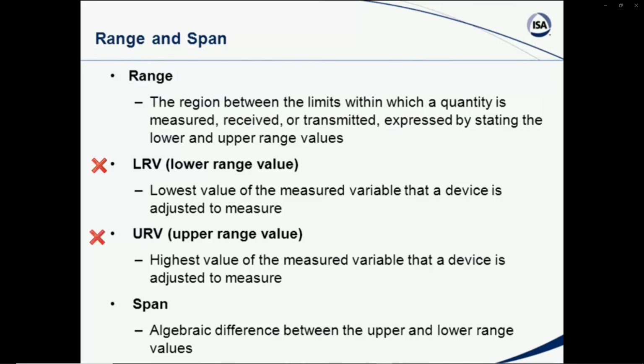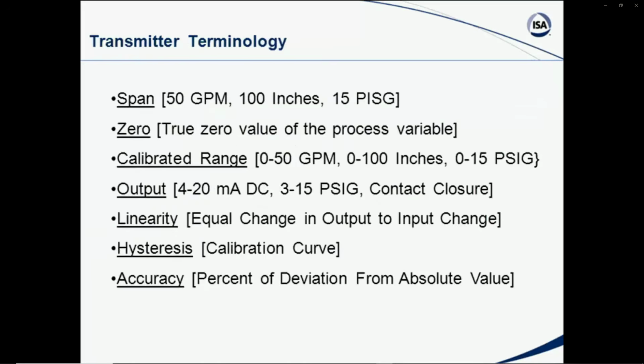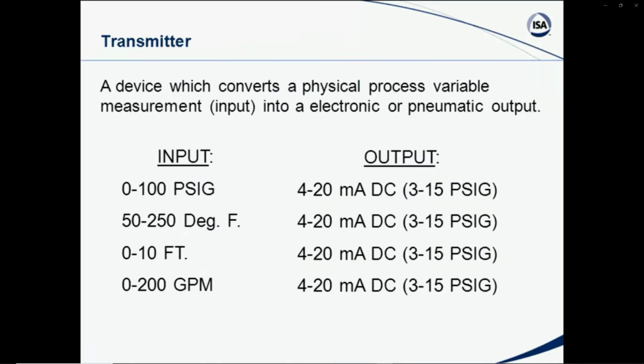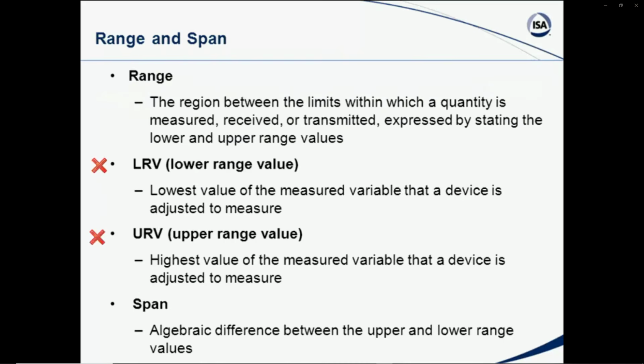Now, if we look back at the prior slide that we had, excuse me, I want to go back to this. In that first case, 0 would be the LRV, and 100 would be the URV for the first situation. And if you look at the others, you would see, for instance, 50 to 250 degrees Fahrenheit, 50 would be the LRV, 250 would be the URV, and so on. So we have LRVs and URVs, and when we say LRV, we do not necessarily mean 0. That is the lowest value of the measured variable that the device is going to measure.